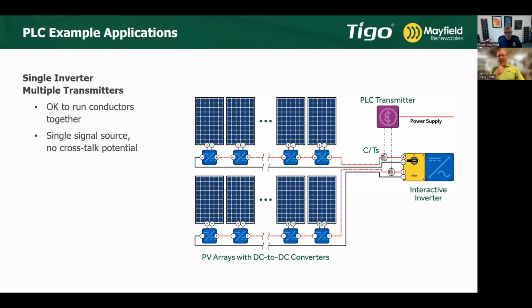Here's another situation, and this is an actual product you can get: the transmitter that has 2 CTs. So you could double what I just said, you could have 20 source circuits coming through, because you have a transmitter with 2 CTs coming off of it, and you could put 10 conductors through each. Depending on the size of your system and how the inverter's connected, this is really a single inverter, single transmitter with multiple CTs. So there's no crosstalk issue, and you're good to go however you wire this up.